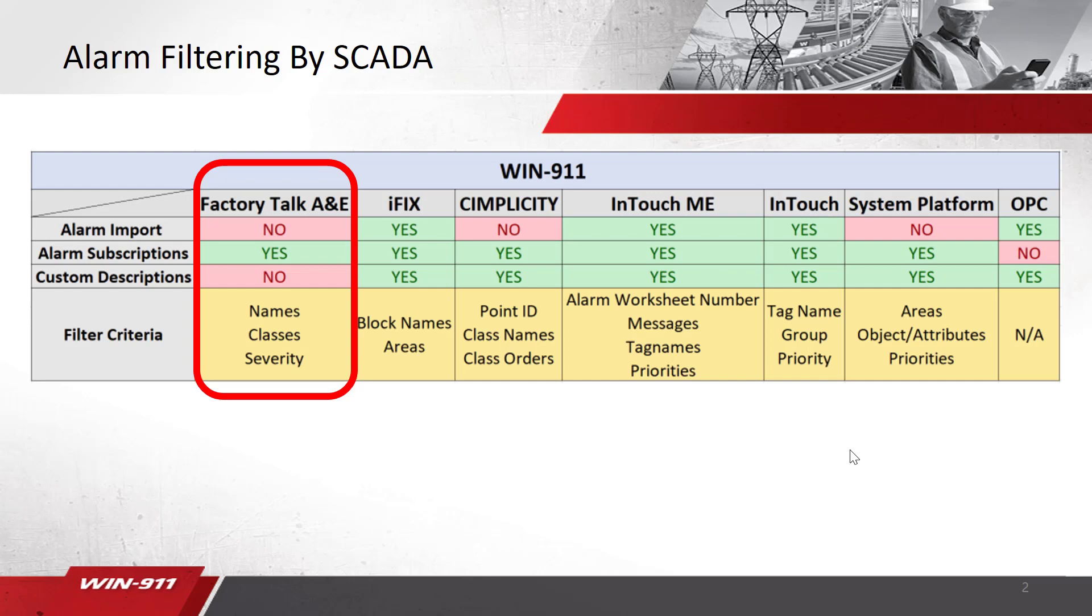Today we will be focusing mostly on Factory Talk Alarm events. For the methods in which you can bring your alarms in, it does not support alarm import, but you are allowed to use alarm subscriptions or filters. We will use that term interchangeably. The method in which you can filter your alarms into WIN 9-1-1 is by names, classes, and severity.